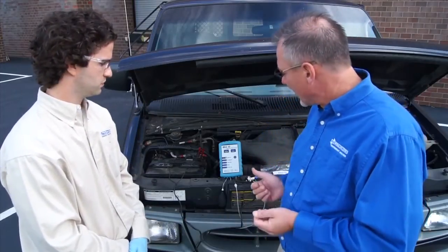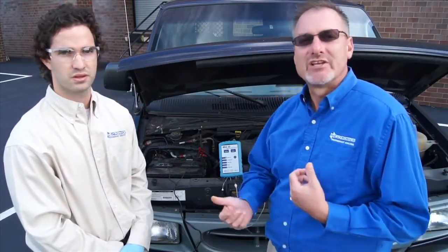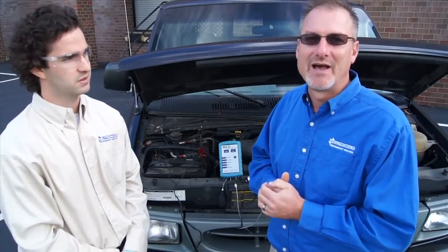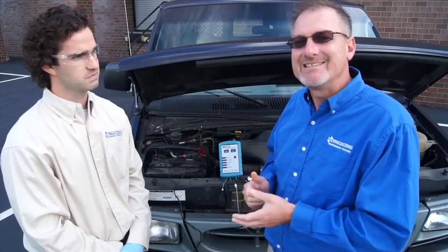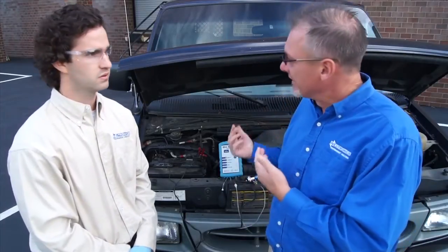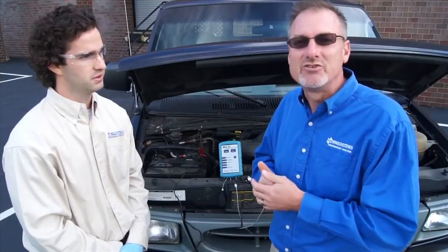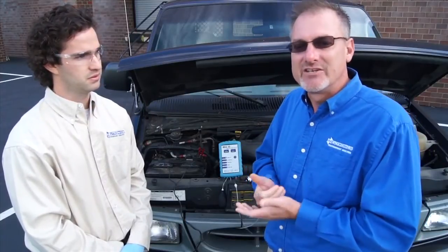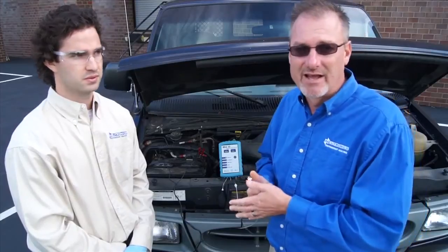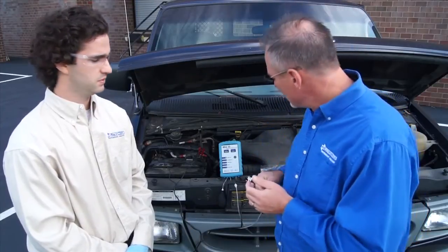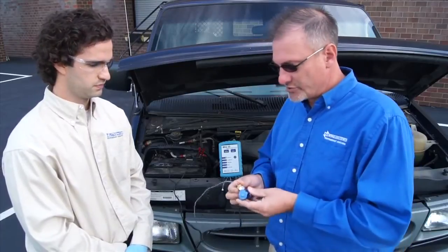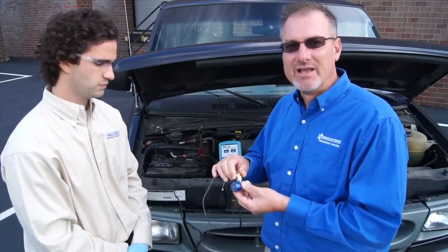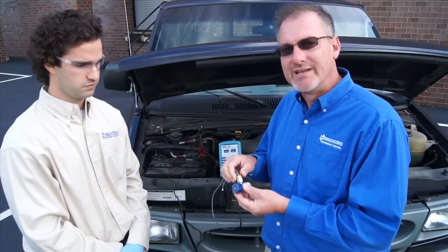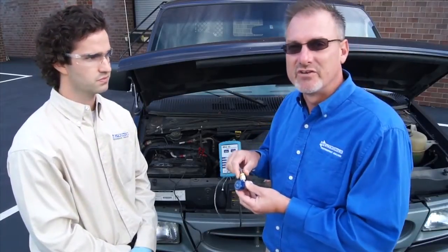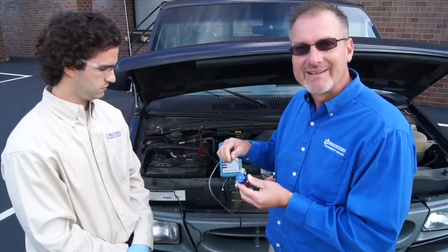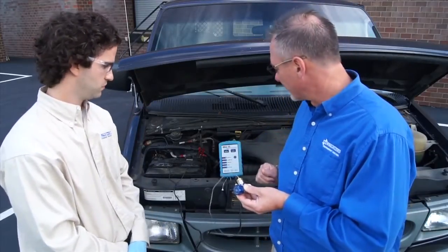So while that's warming up, we want to mention that we just finished episode 2 of our tips and tricks, and we talked about filters and when to change the filter. This is the only refrigerant identifier model, well, this and the Mini 22, that do not use the white sample filter. This unit, along with our new series of analyzers, the RI 2012 series, use a flow restrictor. The flow restrictor is embedded here in the coupler, and this reduces the flow of refrigerant and stops or slows the migration of any oil far before it ever gets to the identifier. So that's why we don't have a white filter on these.